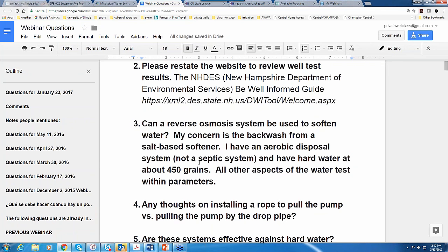The softening process is an ion exchange process where it switches out calcium and magnesium primarily, and a few other things, but they exist in the highest concentration generally. They switch out calcium and magnesium for sodium. It doesn't really remove the overall minerals. You'll see some explanations of softeners that say it's taking out the hardness minerals from your water. That part is true, but it doesn't really take them out completely. It just exchanges them for sodium and causes less scaling ability, and the spots tend to be easier to remove. But the minerals still exist.